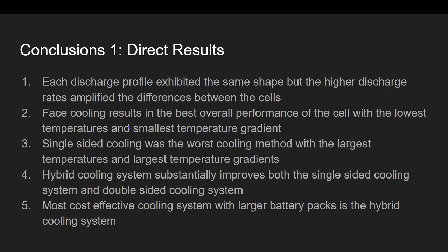We determined that face cooling had the best overall performance, with the lowest temperatures and smallest temperature gradients. We also determined that single-sided cooling was the worst, with the largest temperatures and gradients. That said, hybrid cooling substantially improved on both single-sided and double-sided cooling, which means that, depending on materials and application, it might be the most effective system, particularly for larger battery packs because it's very scalable. So hybrid cooling may be the best option in some applications.